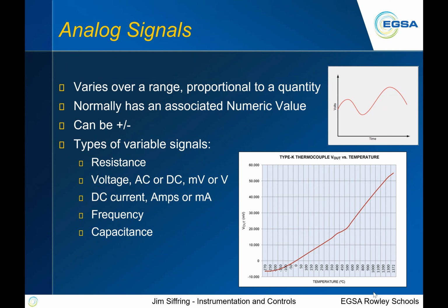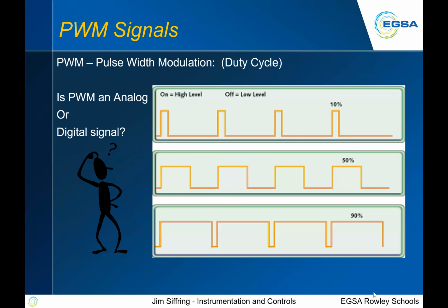So what are variable signals? Resistance, voltage, DC current or AC current, frequency, capacitance, all kinds of different signals. One final one I want to make sure you're aware of is PWM, pulse width modulation. If you look at the upper line, you'll see it's on for 10% of the time and off for 90% of the time. You'll notice that the upstroke of that square wave is the same on all three graphics. And so the frequency is the same.